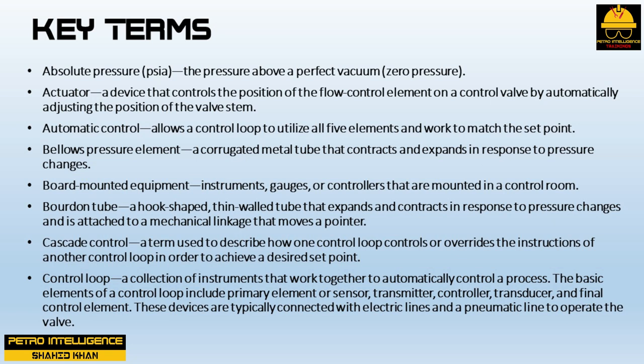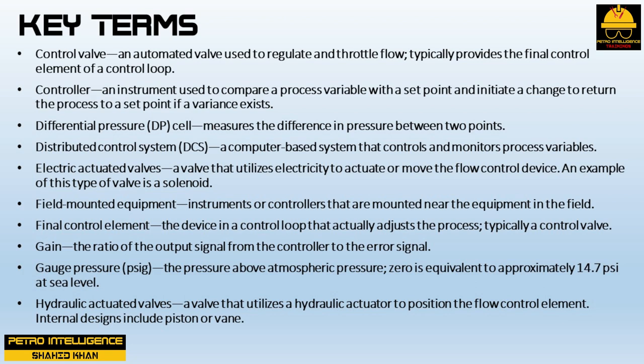These devices are typically connected with electric lines and a pneumatic line to operate the valve. A control valve is an automated valve used to regulate and throttle flow, typically providing the final control element of a control loop. A controller is an instrument used to compare a process variable with a set point and initiate a change to return the process to the set point if a variance exists. A differential pressure (DP) cell measures the difference in pressure between two points.